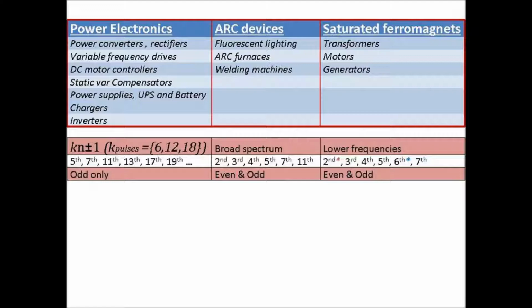There's not too many devices around these days that don't have some sort of power converter in them, whether it be rectifiers, power supplies, UPS, battery chargers, inverters, all that sort of stuff. As that is starting to come onto the system, all your laptops, your TVs, your wind turbines, whatever it happens to be, they introduce new harmonic currents at various frequencies. Then if that interacts with the system impedance, you can have harmonic voltage distortion. So just to give you a feel for the harmonics in question.